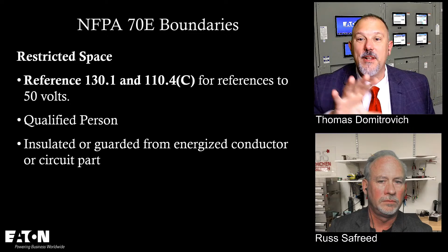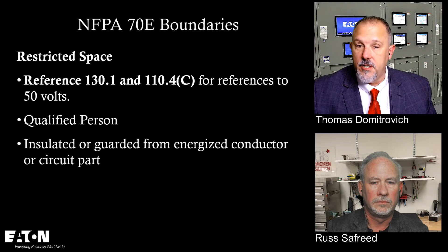Now, Ryan points out you can have an arc flash hazard. So let's think about that. Less than 50 volts, can I have an arc flash? And the fact is, yes. But the arc flash boundaries are so small and the energy is so low. I can draw a spark and say that was an arc flash, so to speak, because it's an arc. It may not have the ability to get a longer distance. I may not have to worry about being 6 feet away. It could be inches. My arc flash boundary could actually be inches.